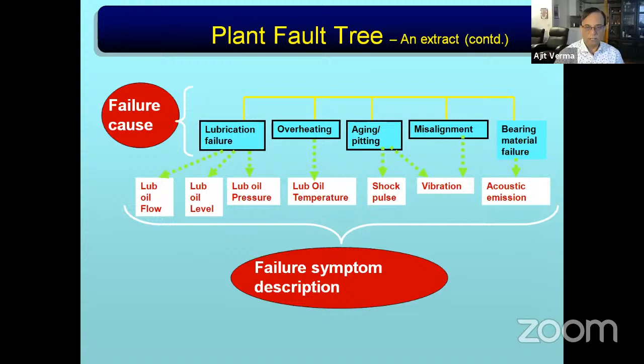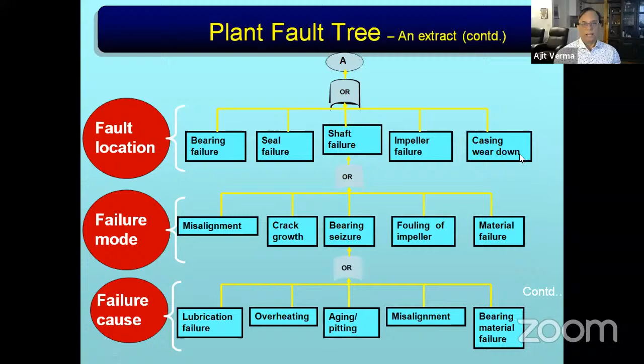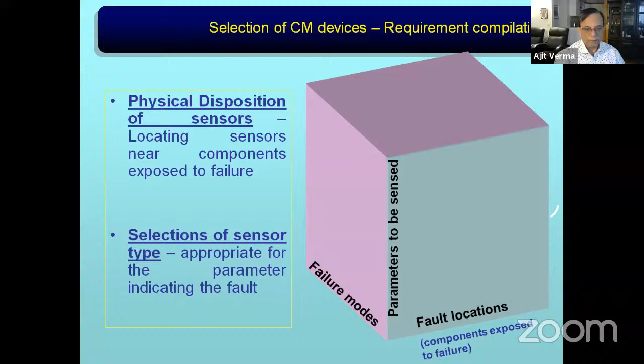For each of them, as we just saw, lube oil flow, oil level, and like that, you have the same for misalignment, crack growth, fouling, and then shaft failure, bearing failure, casing wear down, and therefore it connects right up to the top event. So you have a whole lot of sensors associated with the various failure modes, causes, parameters, and the locations at which the components are exposed to failure. You have this complete matrix of sensors which have to be deployed. So you locate sensors near component failures, and then select sensor types on certain bases: availability of technology, supportability, redundancy, cost effectiveness. So we can move further.